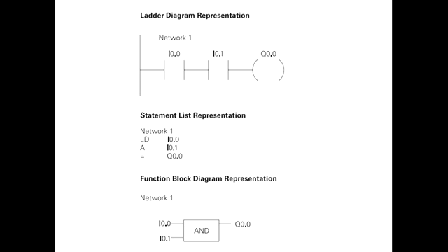An operation. Each rung or network on a ladder represents a logic operation. The following programming example demonstrates an operation. Two contact closures and one output coil are placed on network 1. They were assigned addresses I0.0, I0.1, and Q0.0. Note that in the statement list a new logic operation always begins with a load instruction, LD.